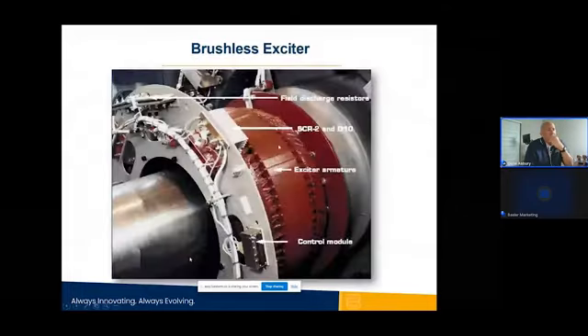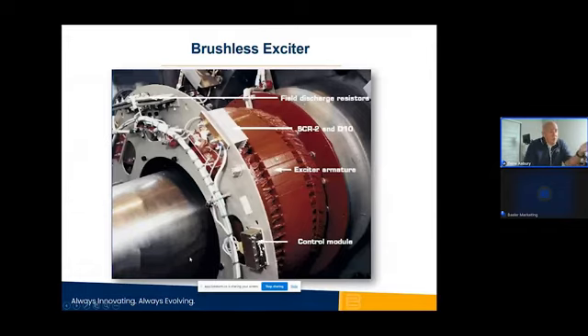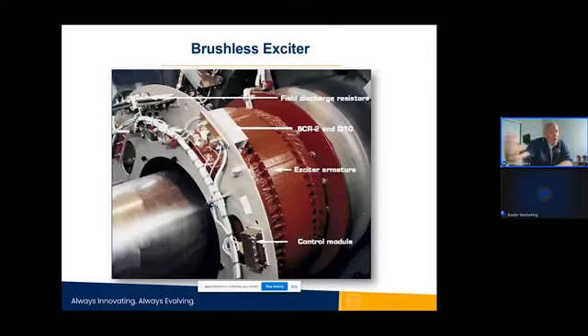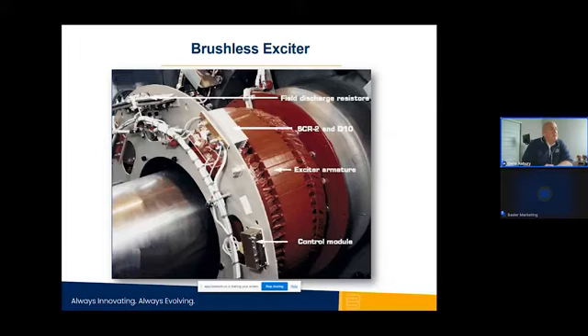So here's a view of a brushless excited motor. Just shows you some of the components: the field discharge resistor, the SCRs and diodes, the exciter armature, the control module, that's the brains behind the operation. The critical part of a synchronous motor is applying the field at the right time. So this control module, and on slip ring motors, as we saw a few slides ago, it would be the field application relay that is applying that field at the right time. And that's when the Basler controls can take over and start regulating power factor. And they also have protective and control means to make sure that motor stays in synchronism.